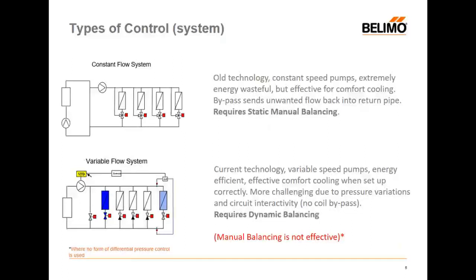It's very energy wasteful because we're producing chilled water, we're circulating chilled water through the pumps, and we're not utilizing all that chilled water because anything not wanted is simply bypassed and returns to the production unit or the heat exchanger. And if it's a production unit, it will undermine the delta of the chiller, and the chiller won't be so efficient and will become more expensive. It also increases the runtime of the chiller and the runtime of the pumps, and they're two major consumers of electrical energy. So not terribly good for the climate or for cost.